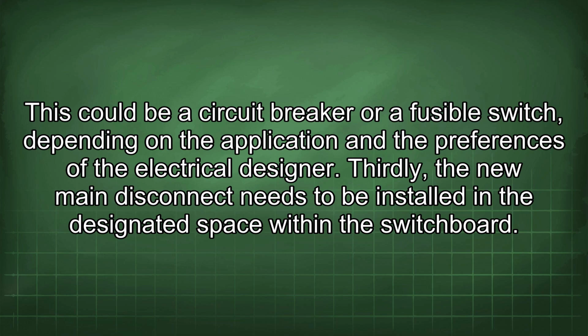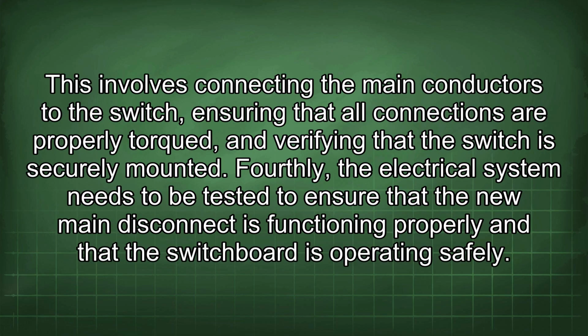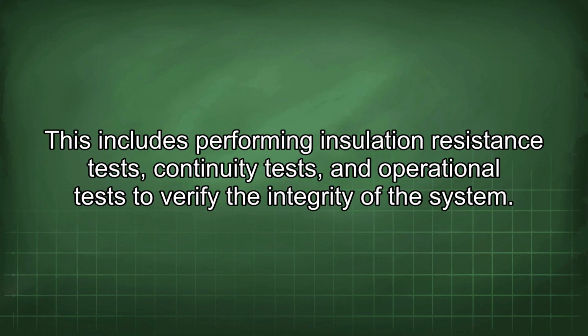Thirdly, the new main disconnect needs to be installed in the designated space within the switchboard. This involves connecting the main conductors to the switch, ensuring that all connections are properly torqued, and verifying that the switch is securely mounted. Fourthly, the electrical system needs to be tested to ensure that the new main disconnect is functioning properly and that the switchboard is operating safely. This includes performing insulation resistance tests, continuity tests, and operational tests to verify the integrity of the system.